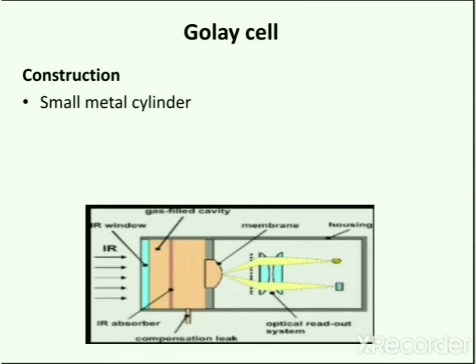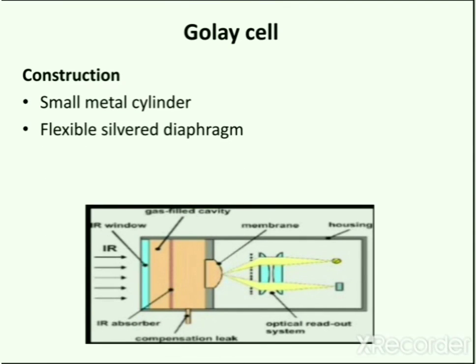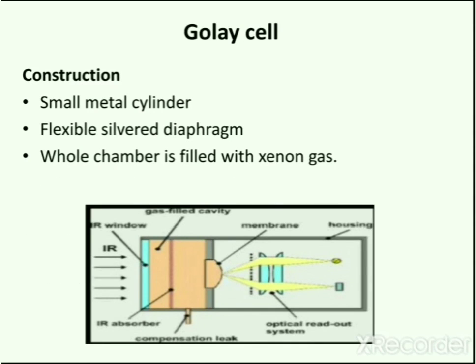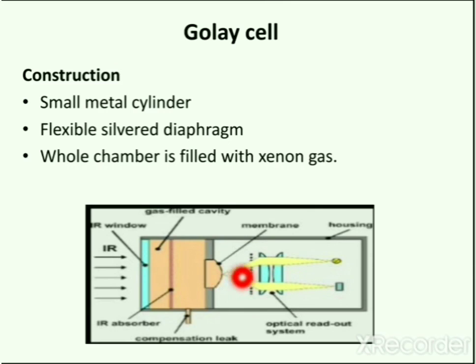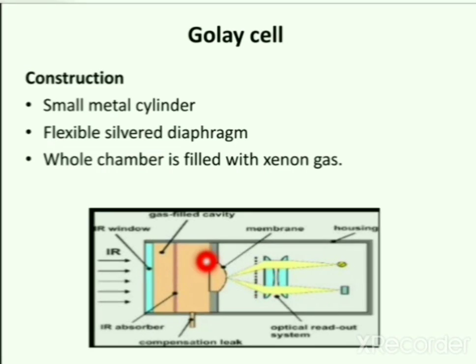The Golay cell is mainly used for infrared spectroscopy. It consists of a xenon-filled enclosure with an infrared-absorbing material and a flexible diaphragm or membrane. When infrared radiation is absorbed, it heats the xenon causing it to expand, and the resulting increase in pressure deforms the membrane. A light continuously reflecting off the membrane is detected by a photodiode, and motion of the membrane produces a change in signal on the photodiode. The detector detects the signal and a spectrum is produced by the recorder.